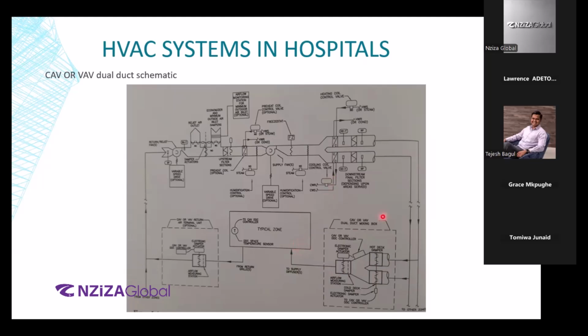Okay, I have a point from Lawrence. I think the ESP, that is the external static pressure calculation, must be done for the critical path. Yes, that is correct. The duct segments and the remotest air terminal, and not the air terminal. Lawrence, you're correct. As I mentioned, once the air goes out of the diffuser, we are considering this as the farthest most VAV box. That is the critical path. Because at the end of the day, if you have the garden hose example that I was talking about, if you take a T out of it before the last point, then the last point becomes your critical path, right? So yes, Lawrence, thanks for bringing that up.